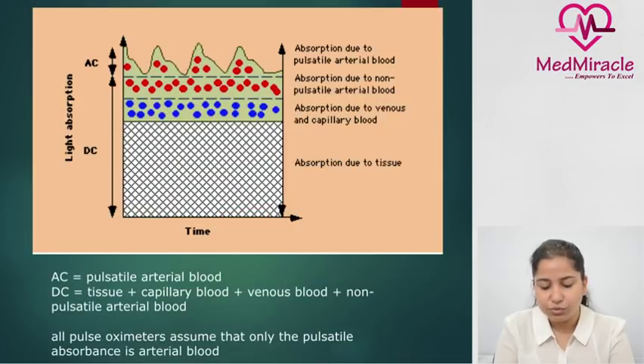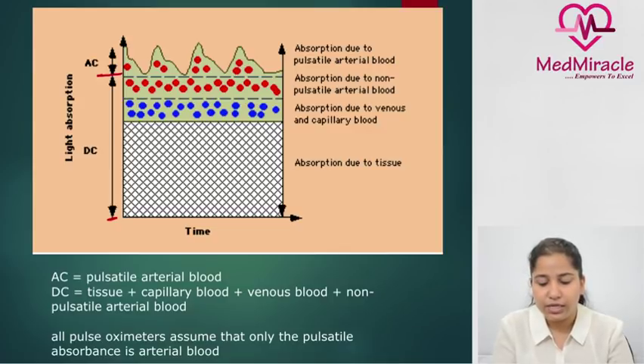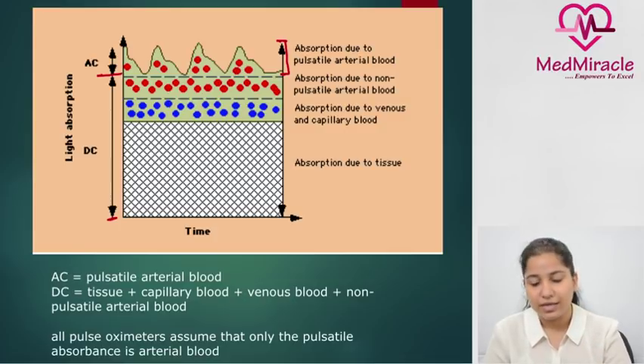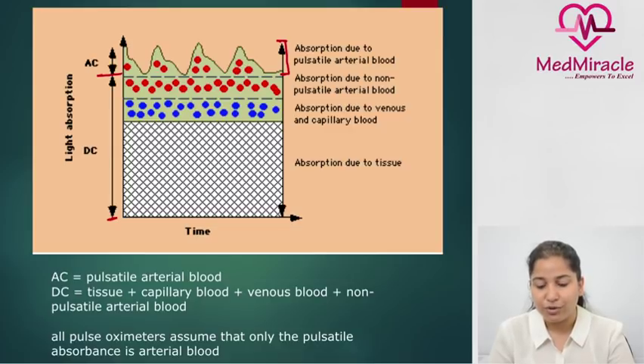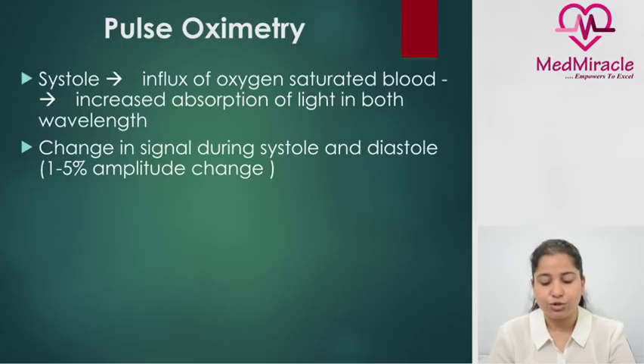Regarding oxygen level in the tissues, there is a pulsatile component and a non-pulsatile component. Pulse oximetry assumes that all blood in arteries is pulsatile, so only the pulsatile part of blood flow is taken as arterial blood and the concentration of oxygen carried by hemoglobin in that part is used for calculation. In systole, there is influx of oxygen-saturated blood into the arteries with increased absorption at both wavelengths. In diastole, there is a slight change in signal of only one to five percent of the amplitude, which does not make a significant change in the SpO2 value.